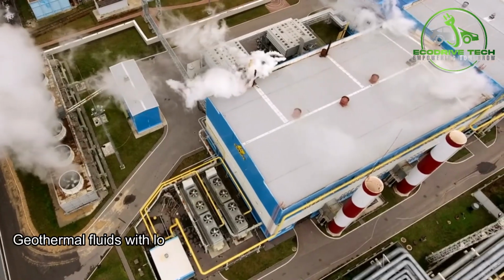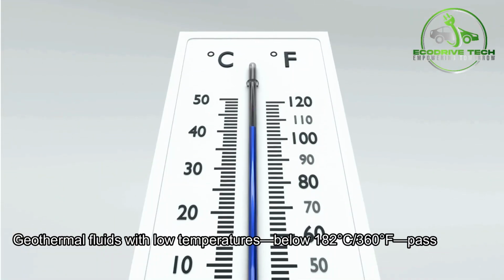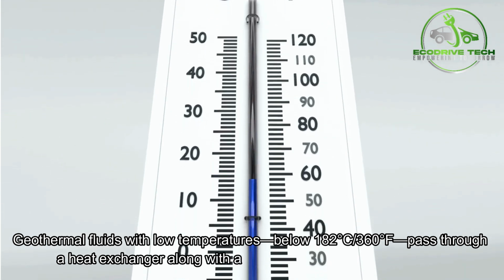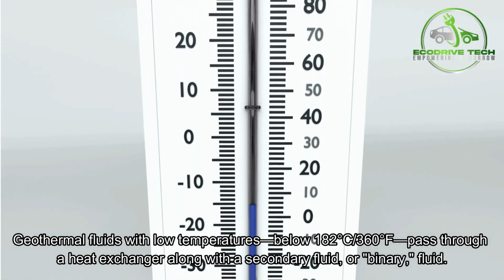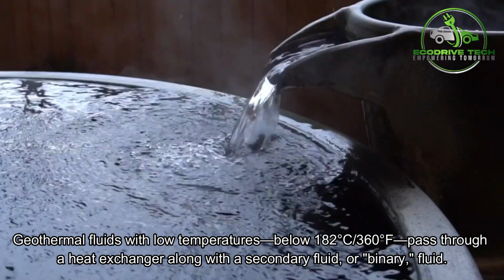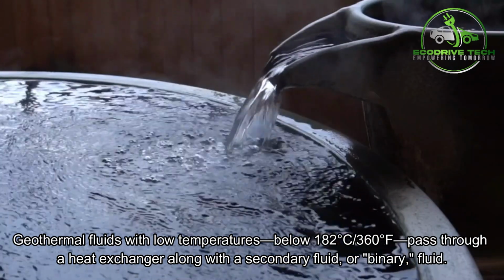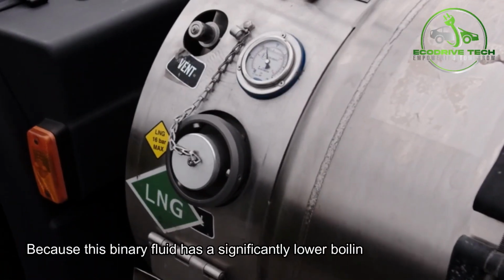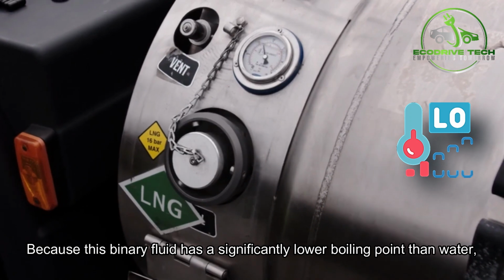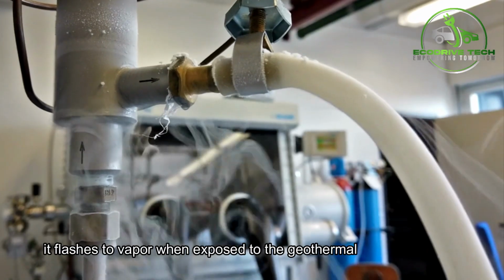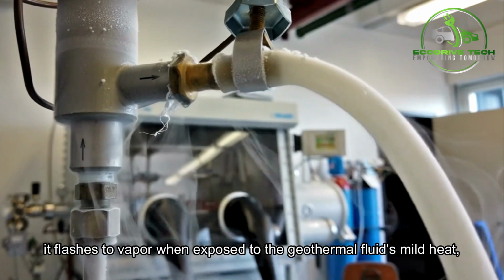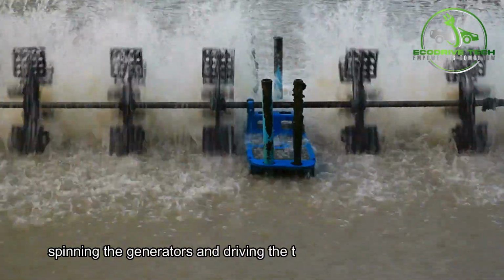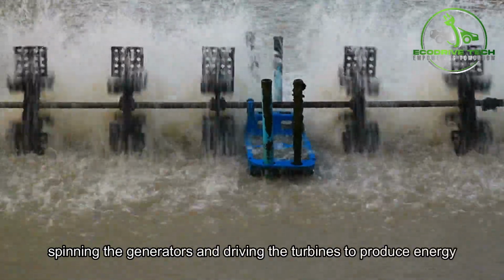Geothermal fluids with low temperatures below 182 degrees Celsius / 360 degrees Fahrenheit pass through a heat exchanger along with a secondary fluid or binary fluid. Because this binary fluid has a significantly lower boiling point than water, it flashes to vapor when exposed to the geothermal fluid's mild heat, spinning the generators and driving the turbines to produce energy.